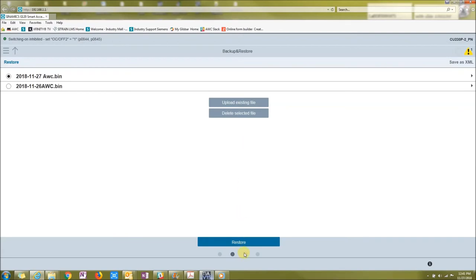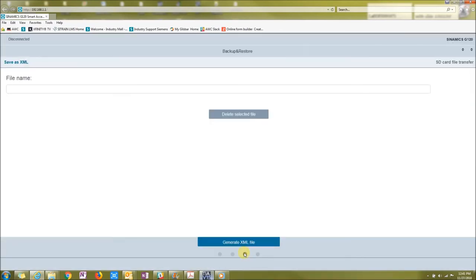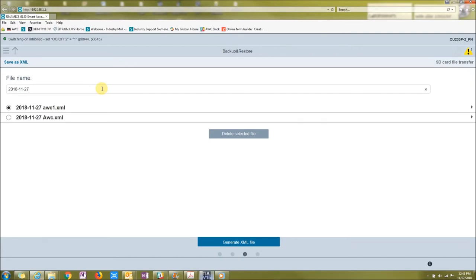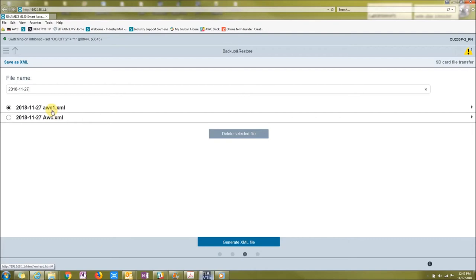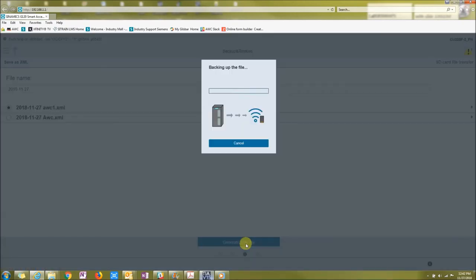Now the third dot, this one you can save the parameter list as a dot XML file so that you may view it. Say if your technician just needs to know what you put into a drive, you can send them this XML file which will have a parameter list with all the values that you've put into it. This is just for viewing and seeing the parameters. Then you can save it offline if you want to. I could generate an XML file and it will save locally on the smart access module up to 20 of them.